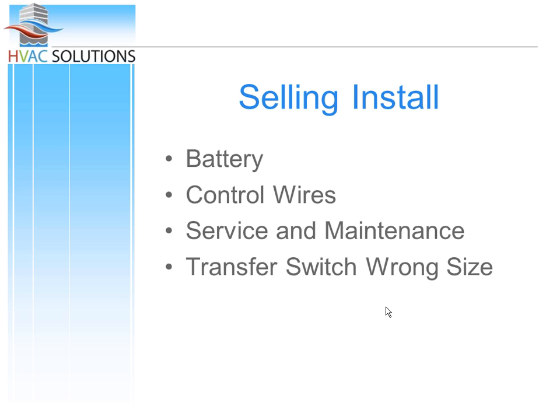Other things to remember with the install: these units do not come with batteries. The battery is a 26R - almost like a deep cycle marine type battery. Control wires - I always talk about this because control wires would mean something like 14 gauge. In the HVAC world, sometimes that means thermostat wire, and you cannot install a generator with thermostat wire. It just will not work.